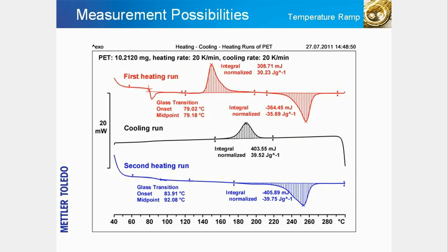Most DSC measurements are performed dynamically using a linear temperature ramp, where the sample is heated or cooled at a constant rate and the different states are measured as a function of temperature. The DSC curves in the slide show typical temperature scans of a sample of amorphous polyethylene terephthalate, or PET. The red curve shows the first heating run. The first event is the glass transition, seen as a step in the curve, followed by an exothermic cold crystallization peak and an endothermic melting peak.